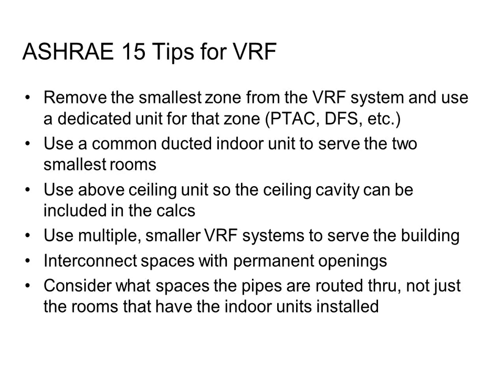So you'll have a good guess of what it's going to be when you design the system, and as long as they don't pipe it differently than what you designed, you will be fine. Lucas asks about refrigerant relief requirements in ASHRAE 15. I'm not so up to speed on that, but let's see if we can. I'm going to save your question for last, and I'm going to pull up ASHRAE 15 on the screen, and we'll look it up.